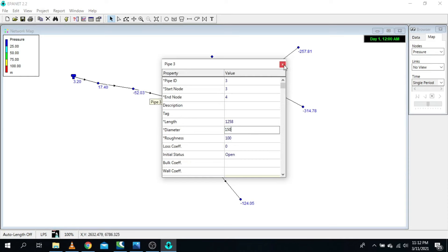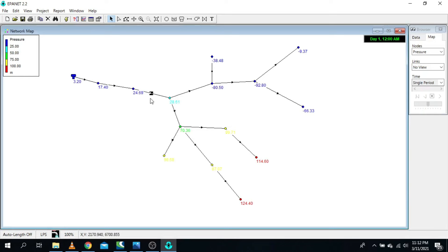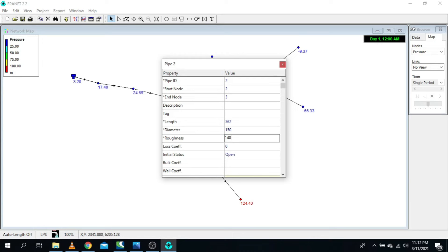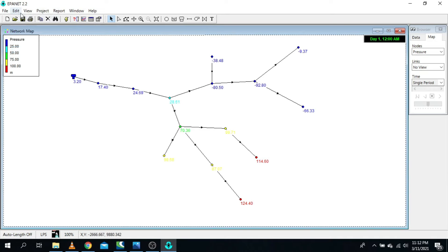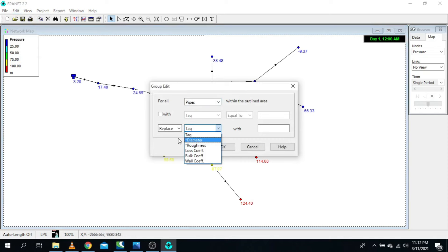Set all gravity main pipes to 150 mm and run again. There are still some negatives in branch sections. Also, we need to change the roughness — our pipes are HDPE plastic and roughness should not be 100. Use Group Edit on all pipes and change roughness from 100 to 140, which is appropriate for plastic pipes. Run again.